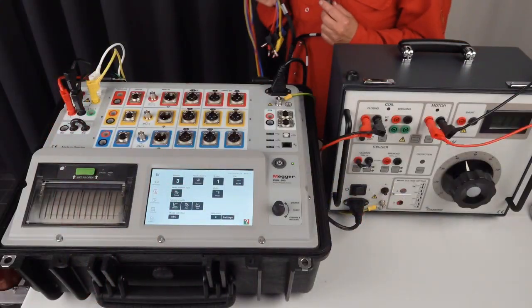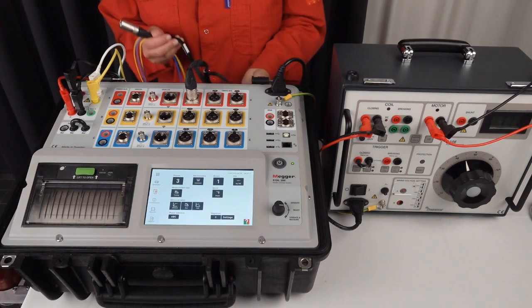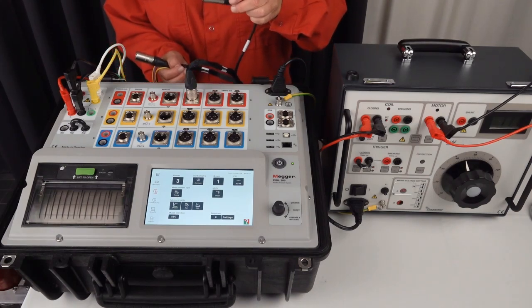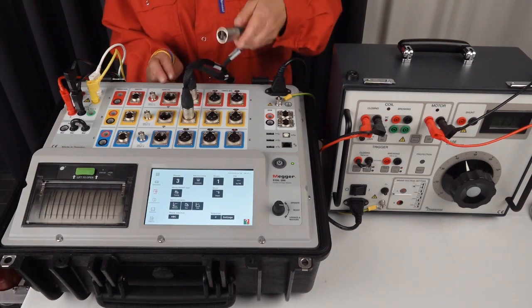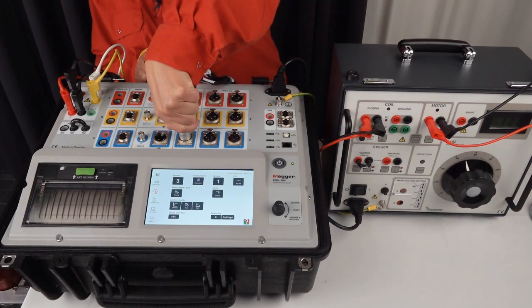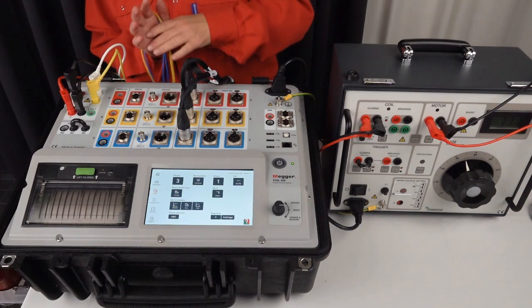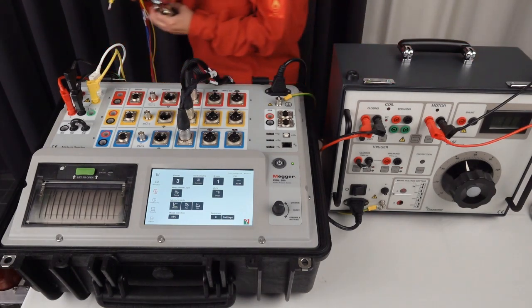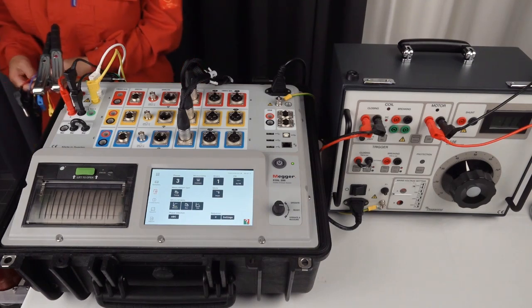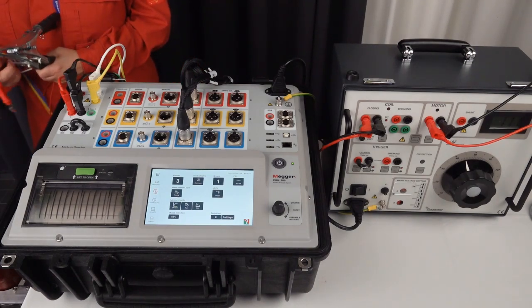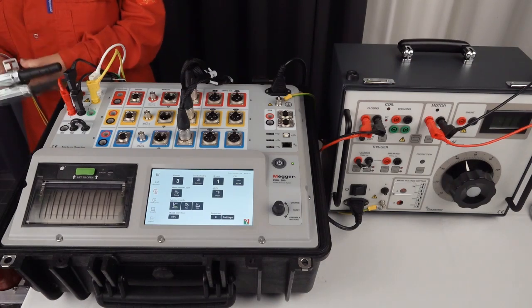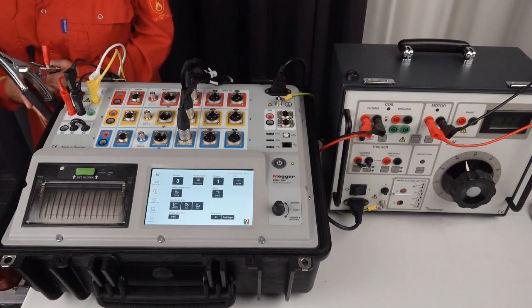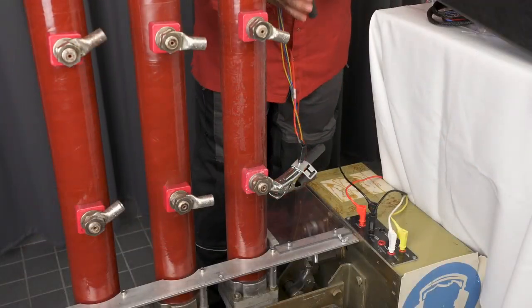I continue with the timing cables. It's a special medium voltage breaker cable. So it is a common cable set for all three phases A, B and C. The cables are color coded and I have a red for phase A and I use the clamps in the system. And I connect on both sides of the pole.